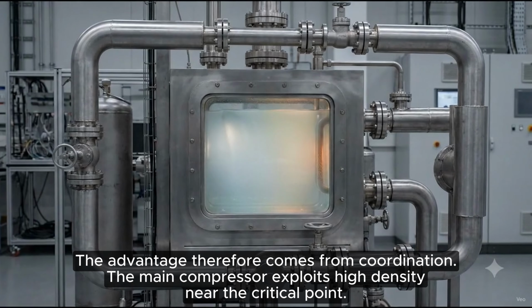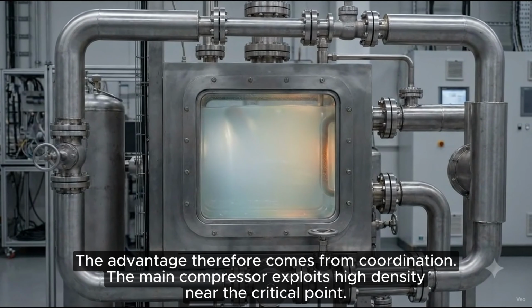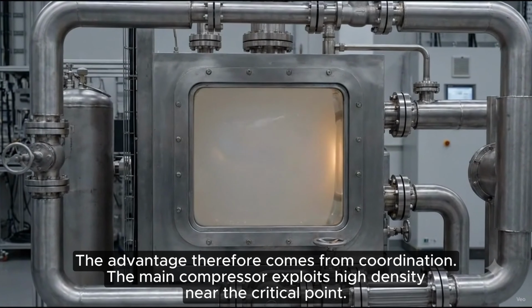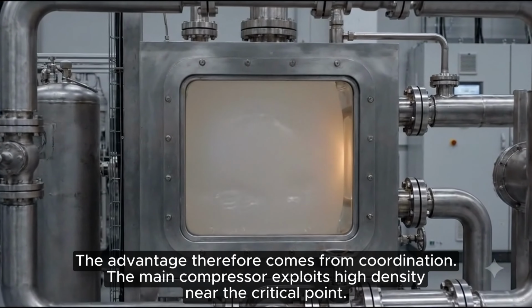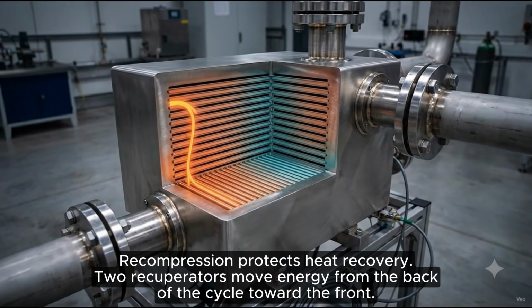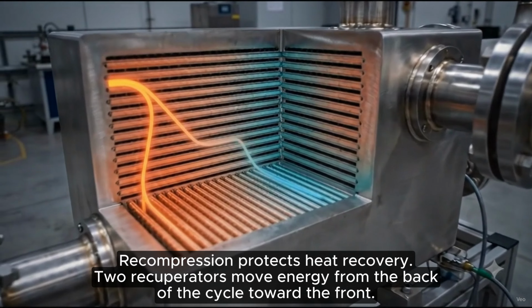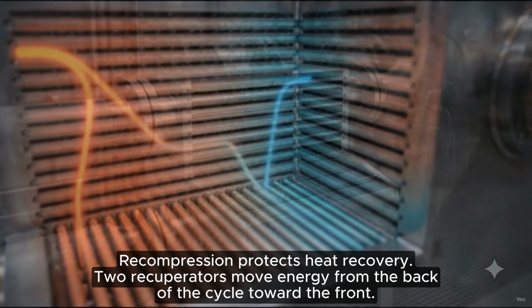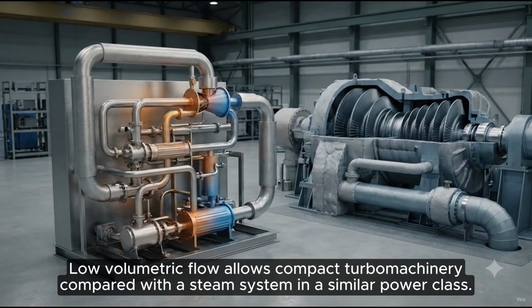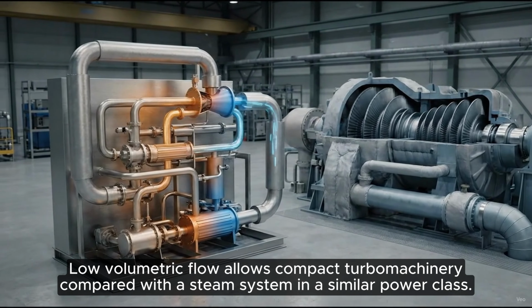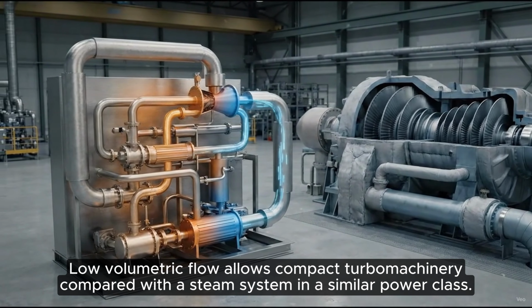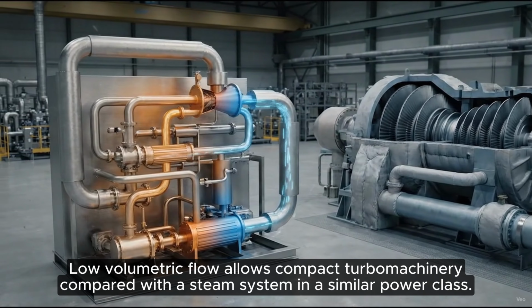The advantage therefore comes from coordination. The main compressor exploits high density near the critical point. Recompression protects heat recovery. Two recuperators move energy from the back of the cycle toward the front. Low volumetric flow allows compact turbomachinery, compared with a steam system in a similar power class.